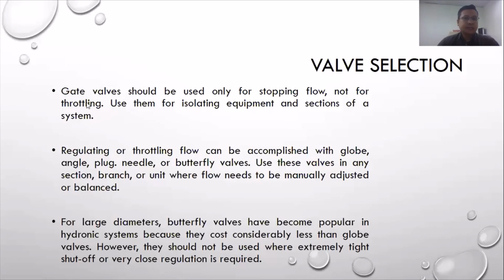Okay, based on the selection, a gate valve should be used only for stopping flow. If we want to do only stopping, please use a stopping type, not for throttling. Regulating or throttling flow can be accomplished with globe, angle, plug, needle, or butterfly valves. These are for regulating. You can choose these. For large diameters, butterfly valves have become popular in hydronic systems because they cost considerably less than globe valves. However, they should not be used where extremely tight, sharp shut-off or very close regulation is required. Okay, please consider this condition if you want to do valve selection.